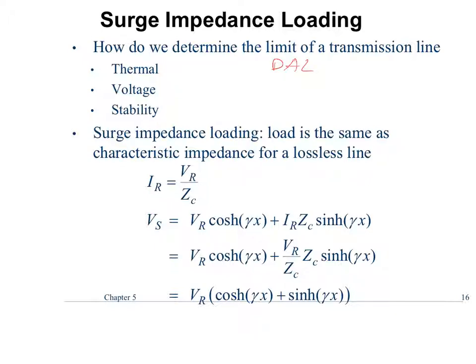That's a term that if you work in the utilities world, you might see it. It is drastic action limit. So when your line is at the limit, well, which limit is it, right? If it's at the drastic action limit, that means you continue to go beyond this drastic action limit, which I think is 5 minutes of operation, you will mess up the line. You will anneal the conductor. You will actually start to change the metal properties of the conductor that's associated with it. So all these transmission lines know what these limits are because you can't exceed those.